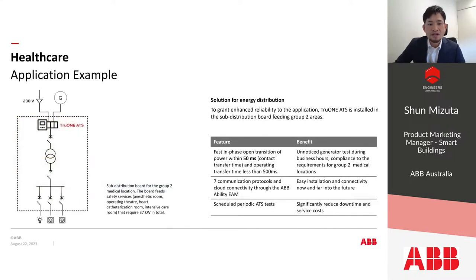This is one example of application. The continuous power supply is one of the most important aspects of hospital operations. IEC defines two groups of patient area: Group 1, body protected rooms, and Group 2, cardiac protected medical locations. For Group 1 and 2 rooms, the IEC standard defines a minimum period of time the backup source shall maintain the power supply for the safety service, and also the change over time. In this specific case of Group 2 medical locations, the ATS has to restore the power within 500 milliseconds. In addition to that, the ATS equipment must be integrated in a monitoring system with cloud-based connectivity. So True One was certainly the perfect solution to be used for this project.